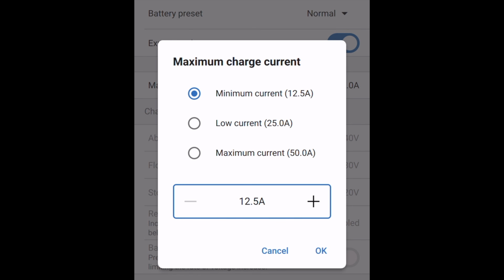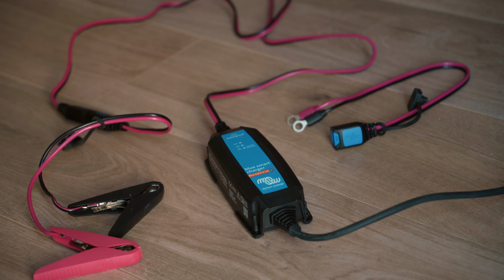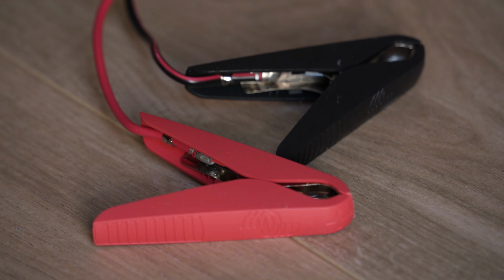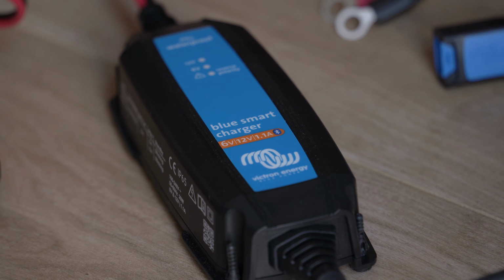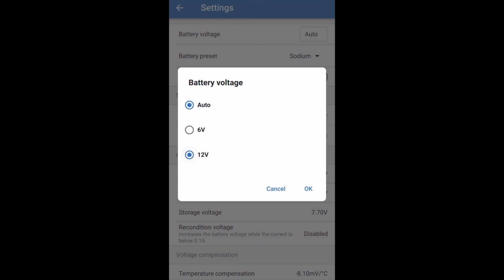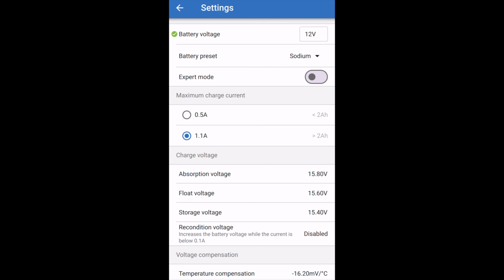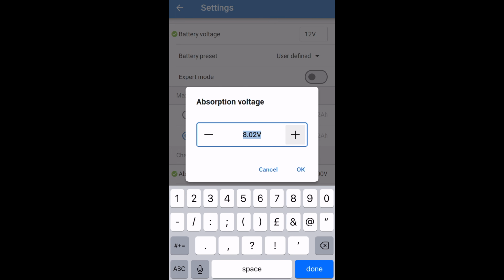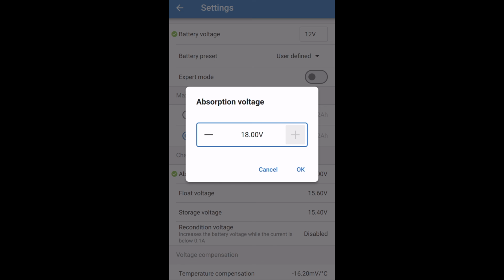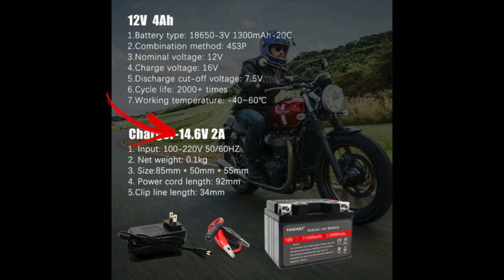The smallest, but still rather clever, charger of the Victron range. It runs at only 1.1 amps when fully wound up. Same control in the app, and importantly we can select whichever voltage we like, even up to 16 or 17 volts. You might not be that animated by this, but for sodium batteries we need high charge voltages, and they are not easy to find. This battery was delivered with a 14.6 fixed voltage wall charger, which cannot properly charge the battery it was sold with. I'm sure proper sodium ion rated chargers will proliferate, but not yet.